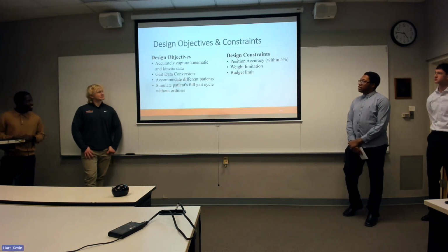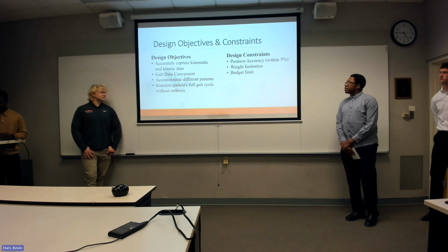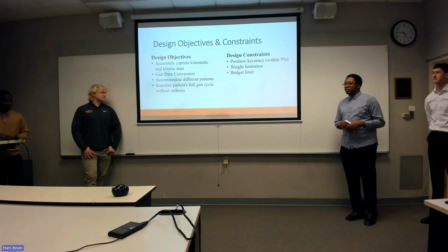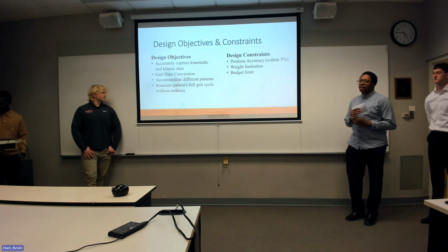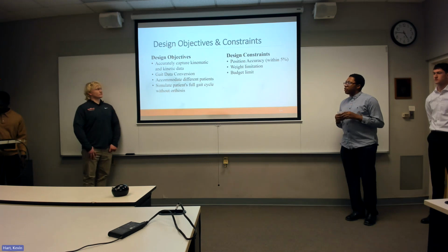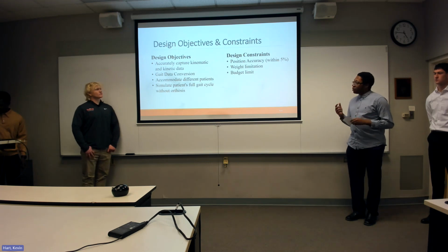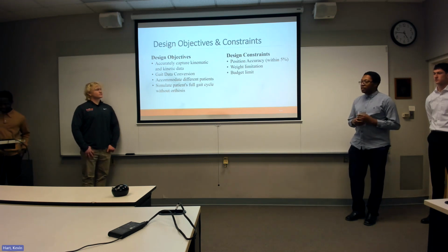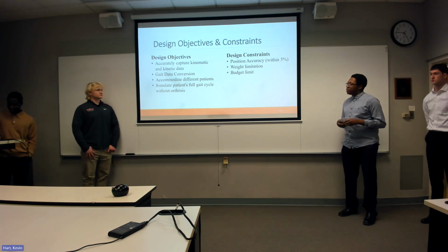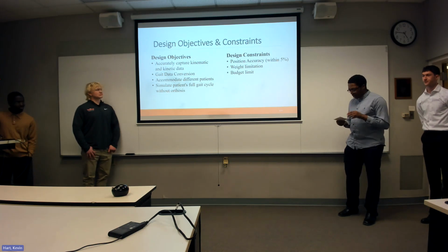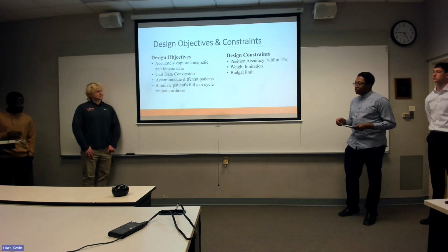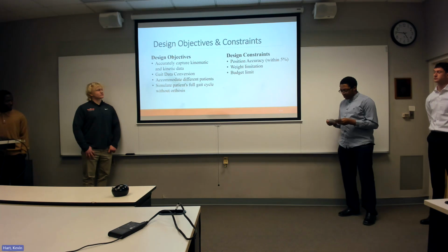So our design is driven by several key objectives. One is to accurately capture the kinematic and kinetic data. This requires high fidelity sensors to measure two distinct types of physics, one being kinematics, which is the geometry of motion. This involves joint angles, velocities, accelerations, and then kinetics being the forces and torques that are present, such as the ground reaction force. This is vital in determining if the orthosis actually corrects the patient's gait.